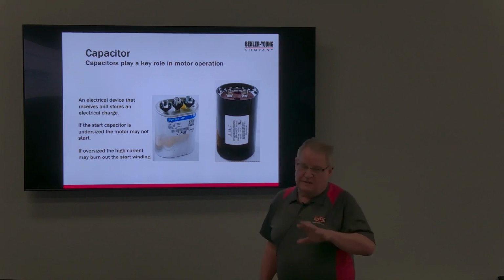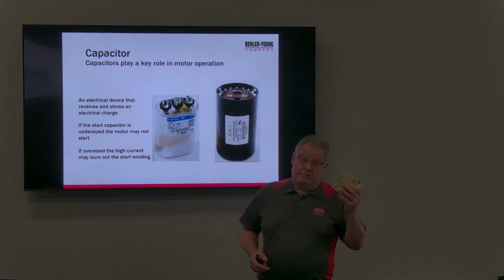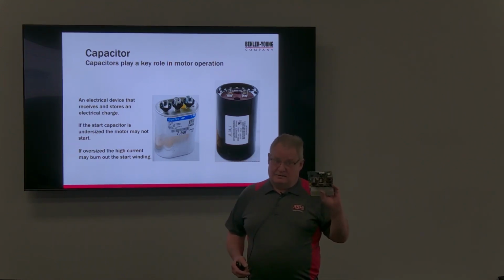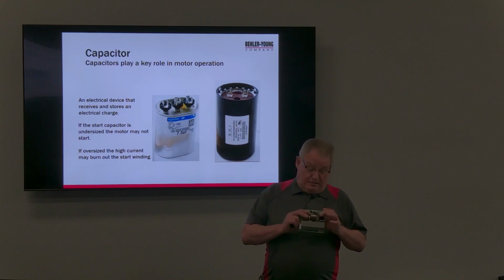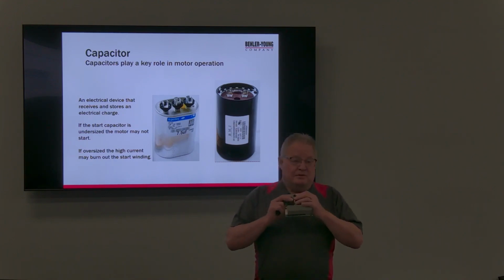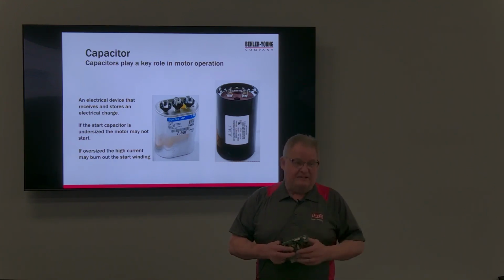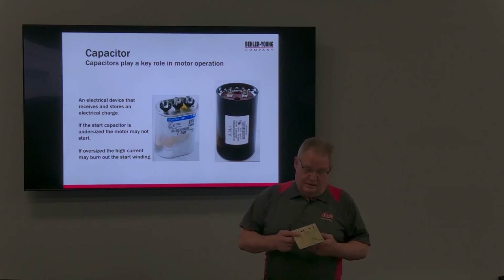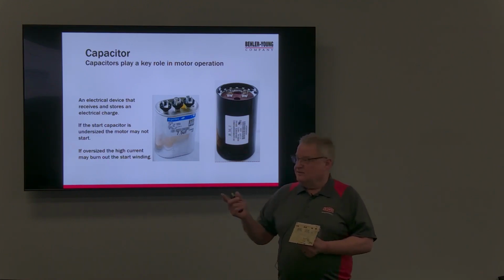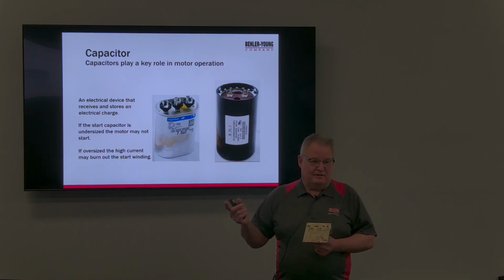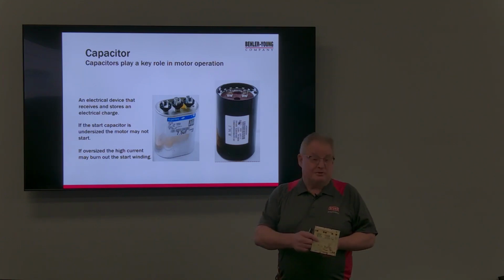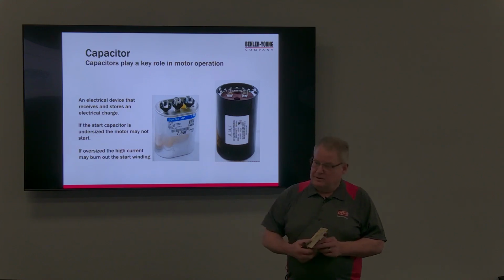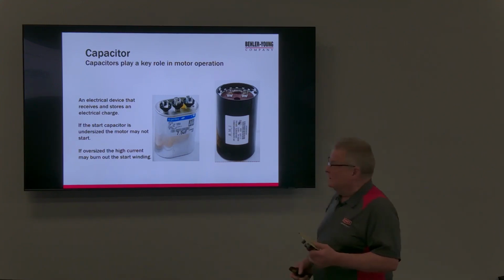So just be careful. Okay, the module on an ECM motor has these. Okay, the inverter board on any of the variable speed compressors has these. Okay, all the mini splits have them. So when you shut those down, wait 5 minutes before you start poking around on those boards. And if you don't got patience, because we're all service people and installers, because we don't have patience, right? Because we don't want to sit in school. So put your meter on there and watch. They say wait till they get down below 50 volts before you start poking around on them. Okay, and they will hold it.